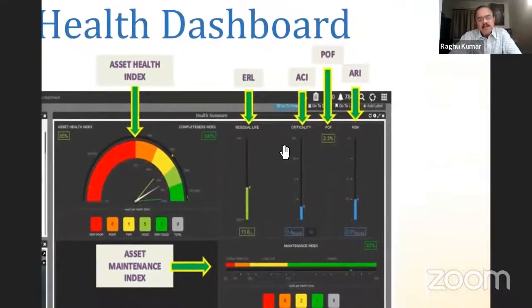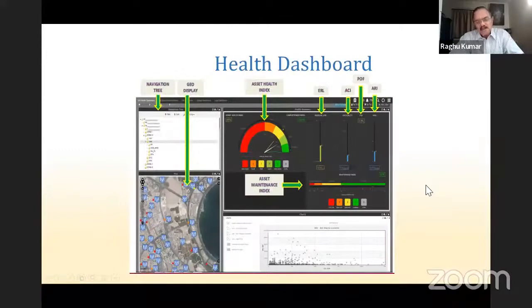Additional information what you get is the expected remaining residual life. In this particular case, it says 13 years more the transformer will live. Then there is something called an asset criticality index. This is a calculation based on a lot of factors like how important the transformer is, how critical the loads are. There are certain formulas for calculating this asset criticality index. And the next one is probability of failure is calculated. Then this asset criticality index and probability of failure gives you the asset risk index. So these are the information which goes for the top management and for the decision support systems. And decisions like whether you should replace the transformer, repair the transformer, upgrade the transformer are all taken based on the health assessment data.